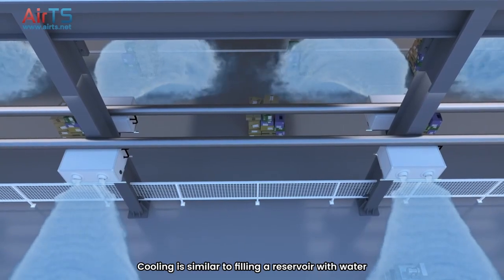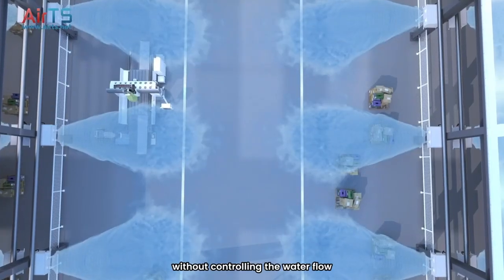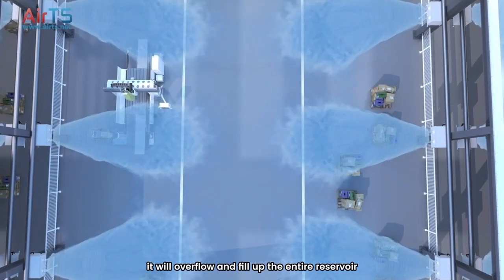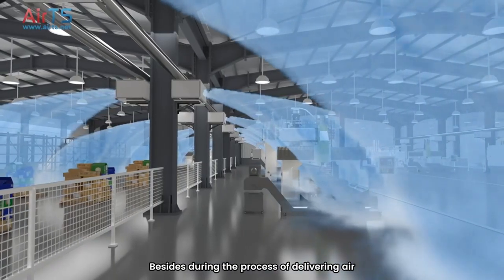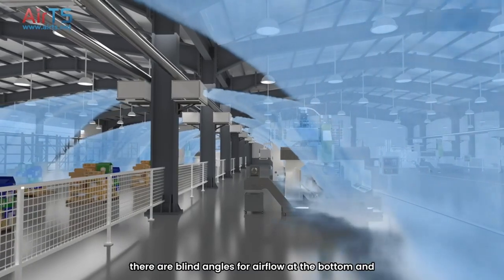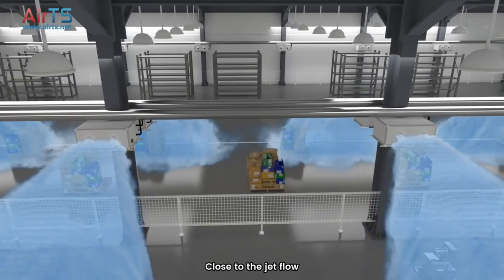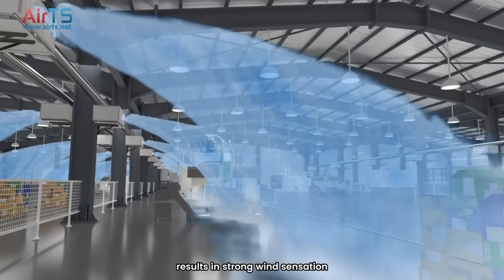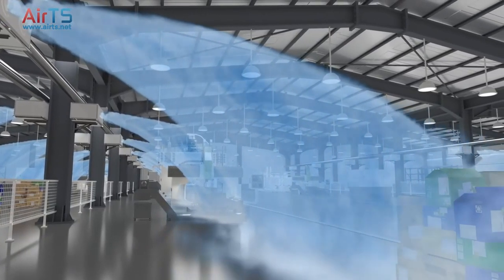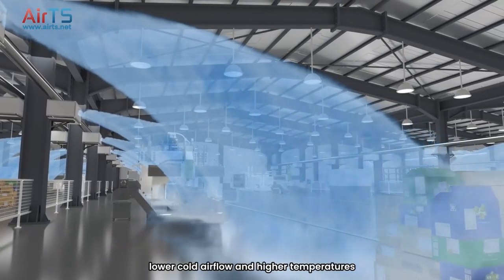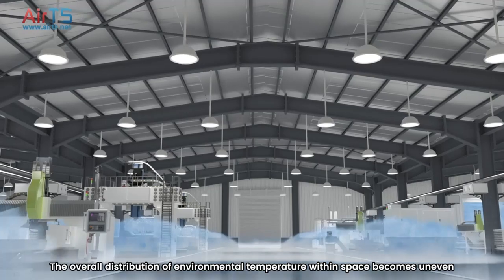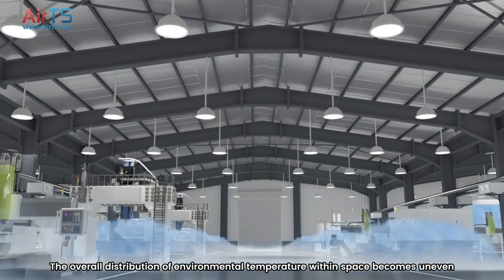Cooling is similar to filling a reservoir with water. Without controlling the water flow, it will overflow and fill up the entire reservoir. Besides, during the process of delivering air, there are blind angles for airflow at the bottom and sides of the device. Close to the jet flow type air conditioning unit results in strong wind sensation, low temperature, and loud noise, while distant areas experience lower cold airflow and higher temperatures. The overall distribution of environmental temperature within space becomes uneven.